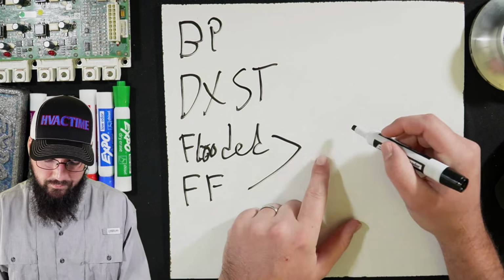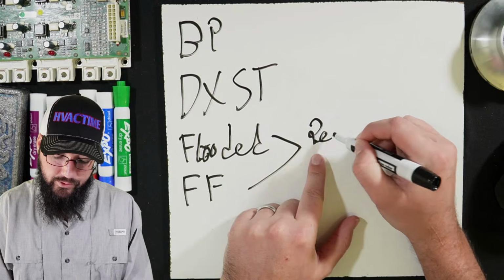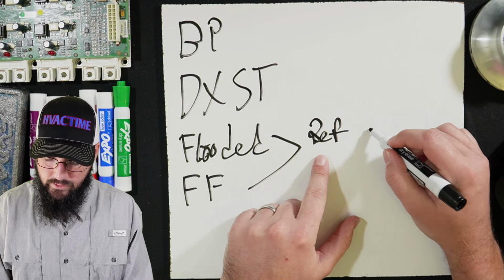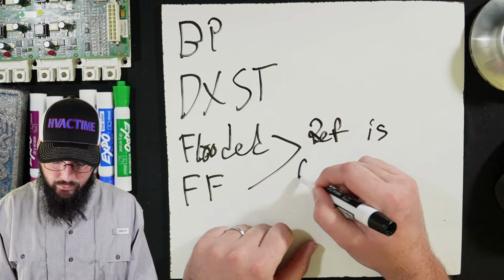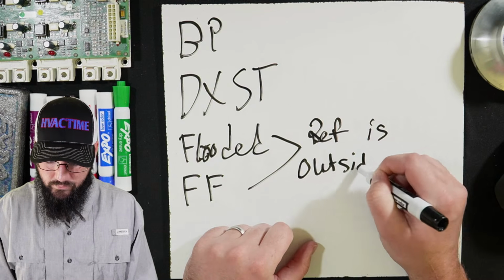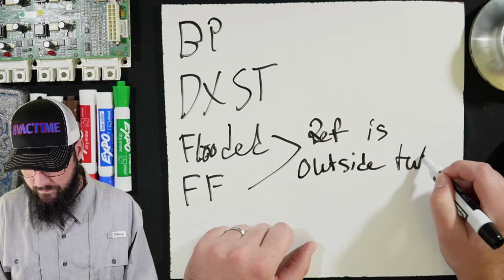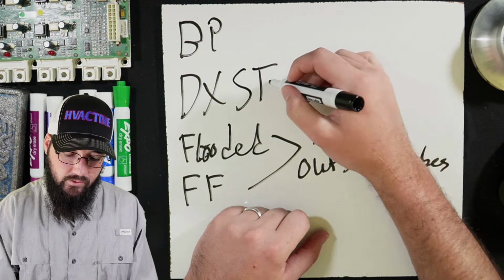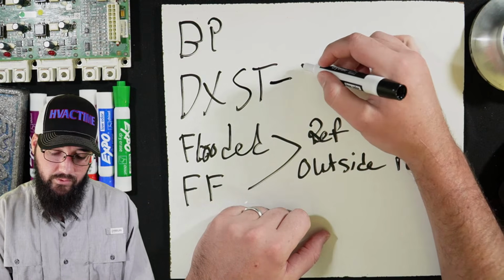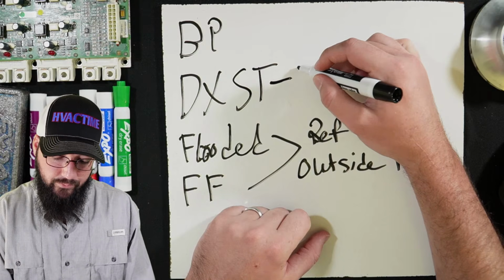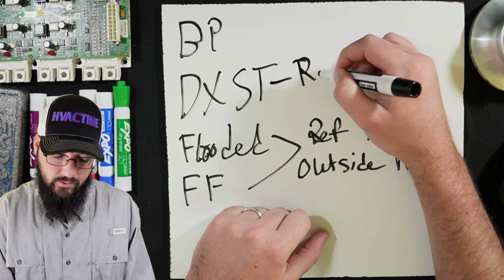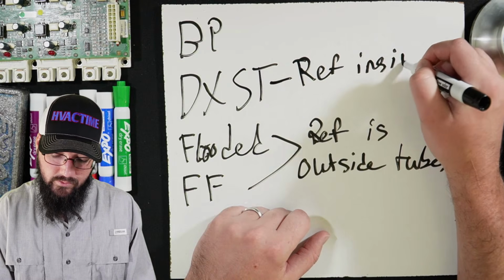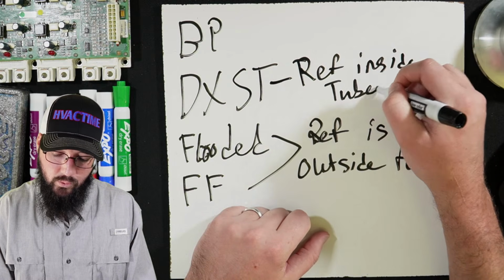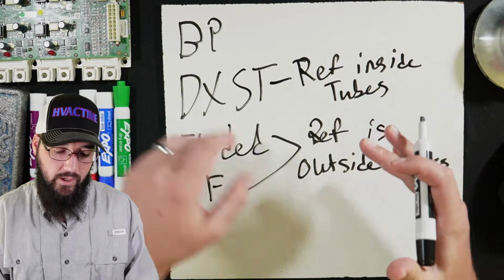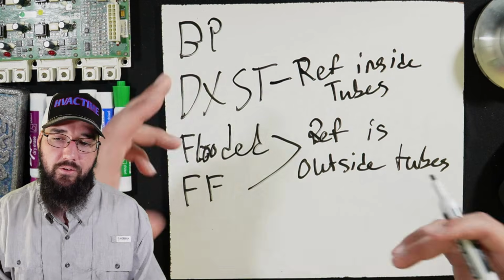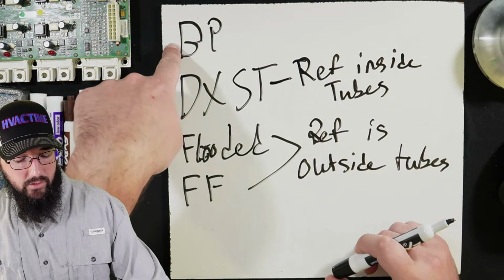These two here, the refrigerant is outside tubes. So it's on the shell side. A DX shell and tube, the refrigerant is inside tubes. And so the water is on the shell side. And then we all know what a braze plate is, or should, ideally.